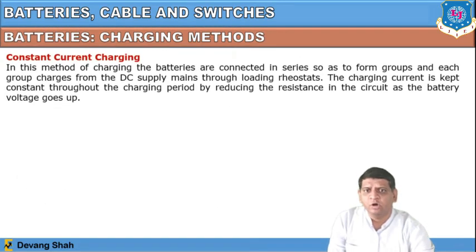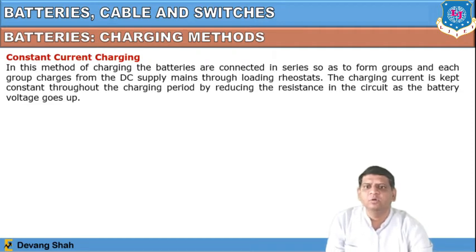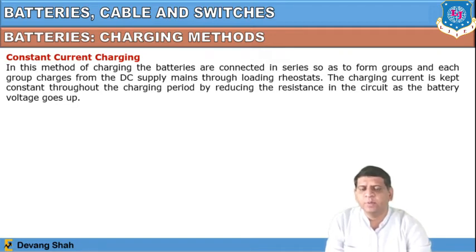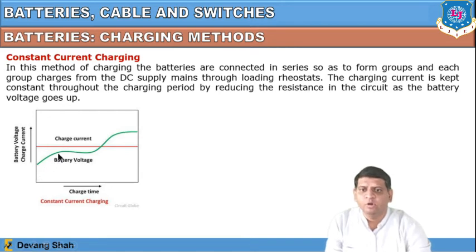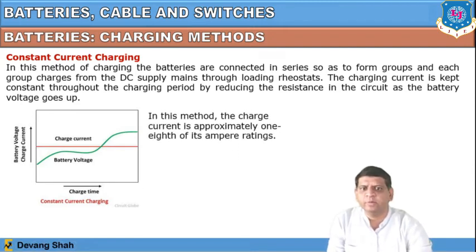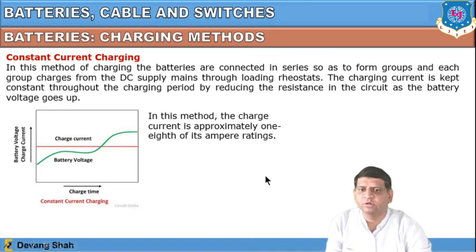The second method is constant current charging, in which the batteries are connected in series to form groups, each group charged from the DC supply mains through a load resistance. Extra resistance is connected when all cells or batteries are in series. The charging current is kept constant throughout the charging period by reducing the resistance in the circuit as the battery voltage goes up — as seen in the graph where charge current remains constant while battery voltage rises from lower to higher value. In this method the charge current is approximately one-eighth of the ampere rating.